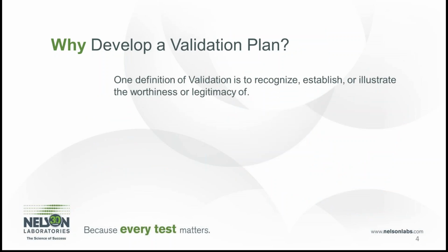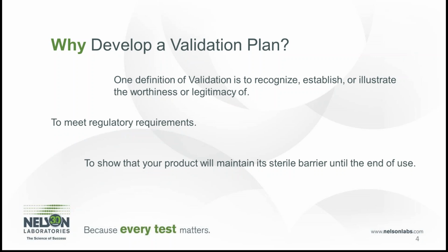So why develop a package validation plan? One definition of validation is to recognize, establish, and illustrate the worthiness or legitimacy of. So by creating a validation plan, you're showing that your package system, your sterile barrier system, is worthy of maintaining its barrier properties until end of use. Also, it is to meet regulatory requirements and to show that, as we mentioned previously, that the sterile barrier is good until it is used.